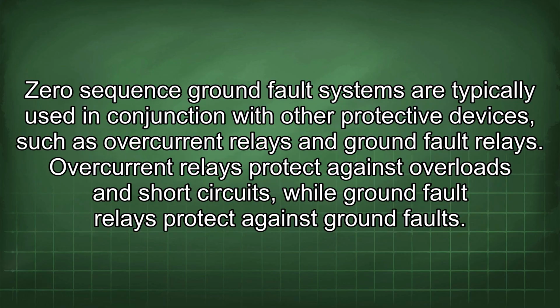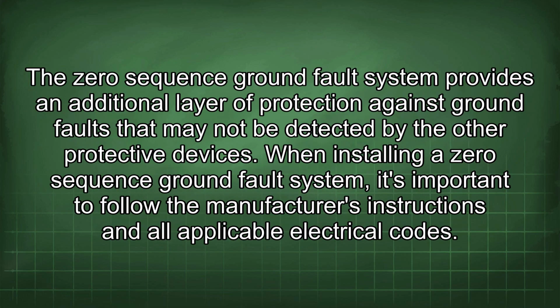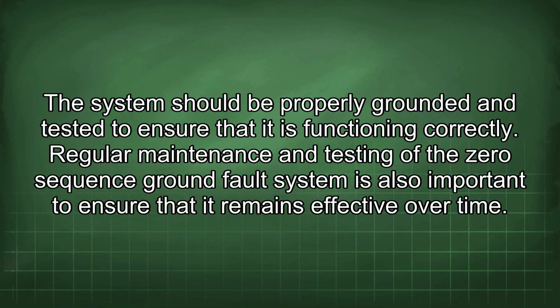Zero-sequence ground fault systems are typically used in conjunction with other protective devices, such as overcurrent relays and ground fault relays. Overcurrent relays protect against overloads and short circuits, while ground fault relays protect against ground faults. The zero-sequence ground fault system provides an additional layer of protection against ground faults that may not be detected by the other protective devices. When installing a zero-sequence ground fault system, it's important to follow the manufacturer's instructions and all applicable electrical codes. The system should be properly grounded and tested to ensure that it is functioning correctly.